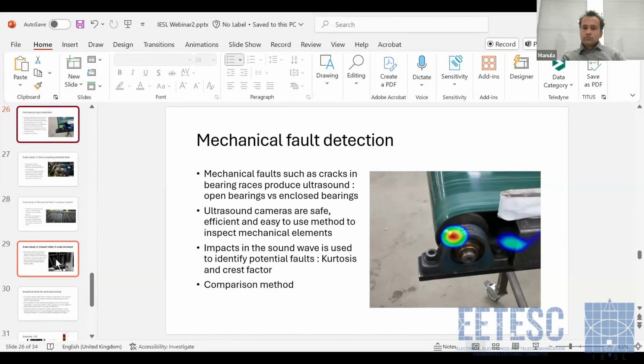Yeah. So these are these kind of open bearings. If there is a fault in the bearing, it might generate ultrasound and it can be detected with airborne ultrasound. But there are applications where bearings are hidden inside. In those cases, it is not practical to use this kind of ultrasound camera to detect bearing faults. For example, journal bearings would not produce ultrasound as well, because those are sliding on these oil layers.